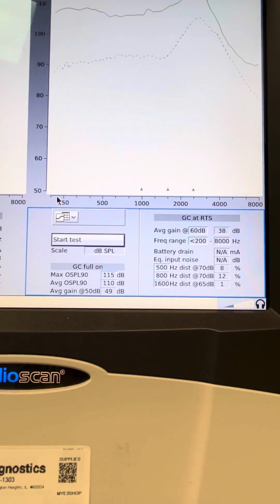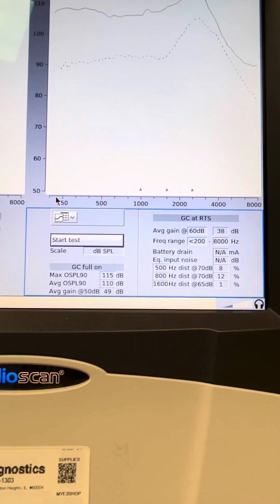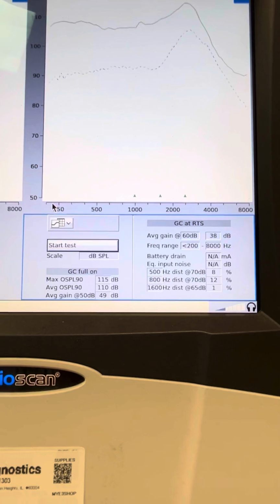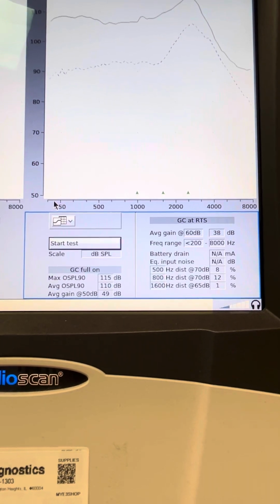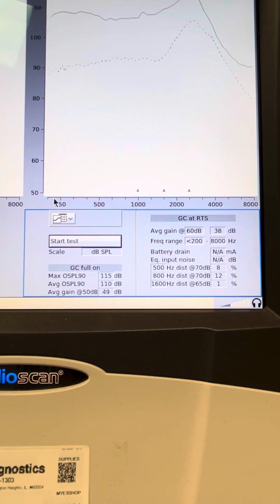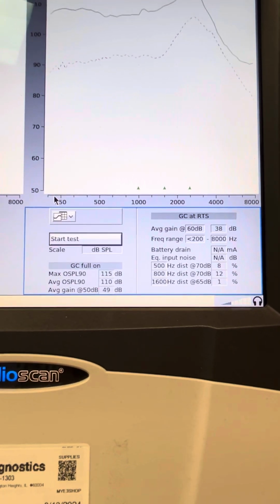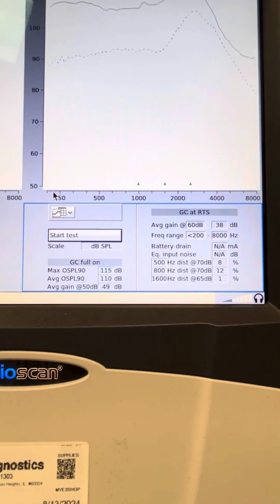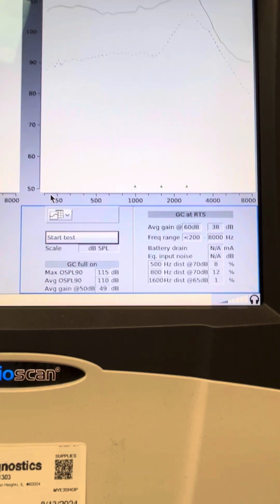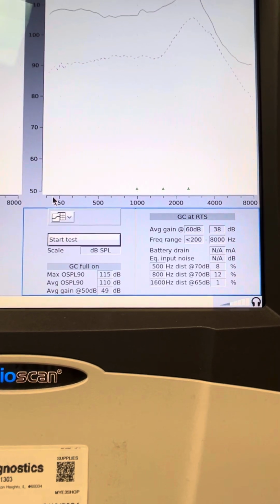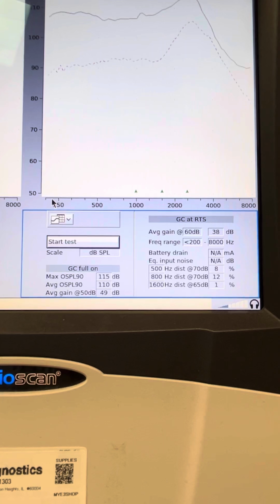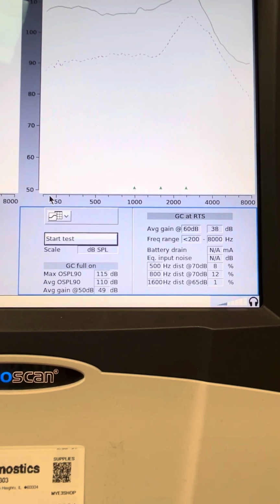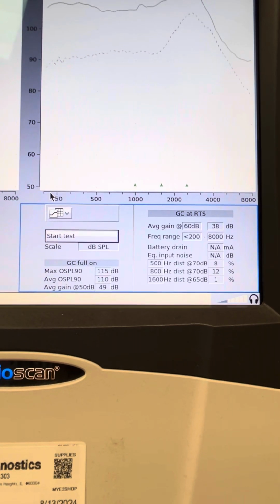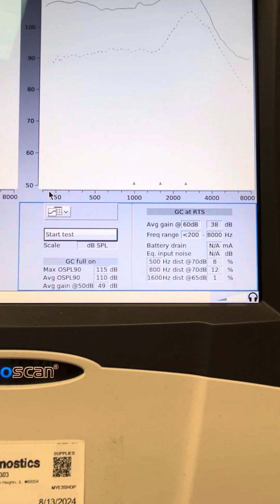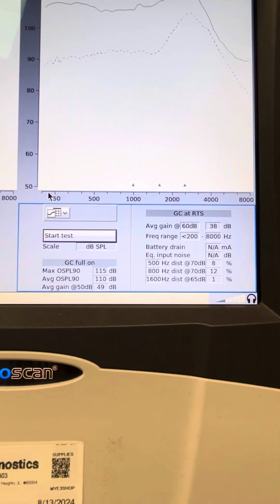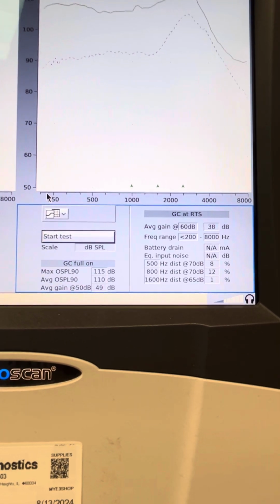Our frequency range on our test was 200 to 8,000, but on the spec sheet, it says it would actually be from 100 to 8,900, so that one is off. And then for our total harmonic distortions, we had 8, 12, and 1. 8 and 12 were way out of specs. 1 is within specs for 1600 hertz. But overall, it's not within specs because of those. But for the first 3, those were all in specs.